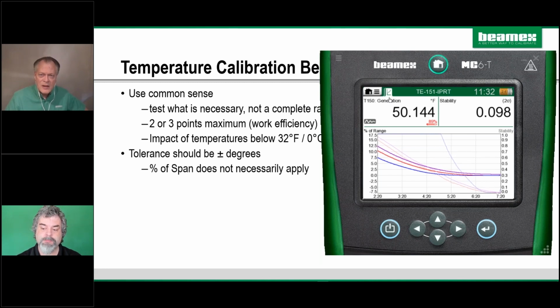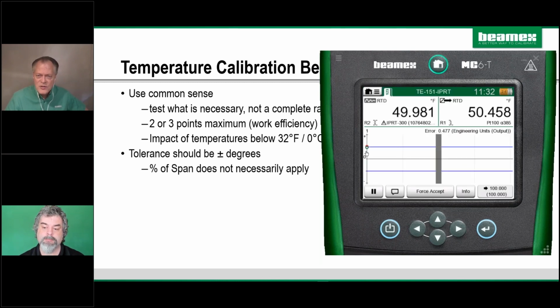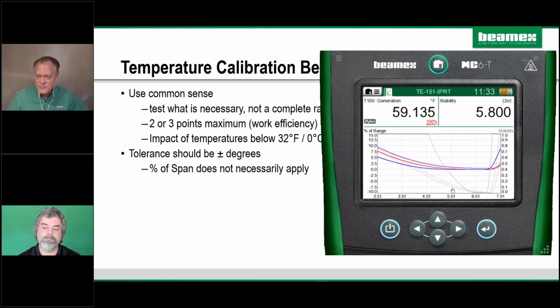So now in fact, let's go over to this. We'll go back to the calibration screen. So it actually, the sensor is going to fail. It's out by 1/2 degree at 50 degrees. So now we've taken our reading at 0%, and now we're trying to get to 50%, which is 100 degrees in this test. So it's starting to run, and let's go back here. So you can see the internal sensor is way faster on the heat.